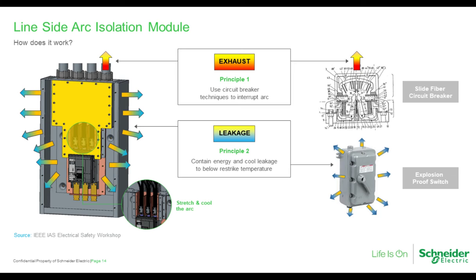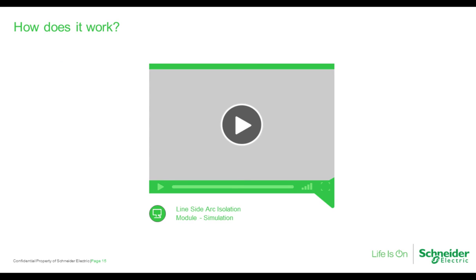This means you can effectively forget about the line side zone 1 incident energy risk and focus solely on the zone 2 side, which is the load side of the breaker, where other techniques like EMS, ERMS, ZSI, and relays are available to further reduce incident energy. Lastly, the reliable isolation of the line side incident energy means that opening the main circuit breaker of the panel effectively establishes an electrically safe condition without requiring opening the next upstream device. This reduces the size of a planned outage to the piece of equipment in question and reduces the impact on the overall facility. So let's see it in action.